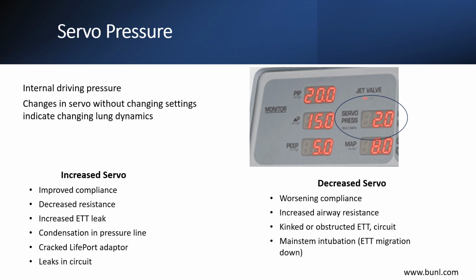This may mean that lung compliance is improving, or there is a leak in the system and gas is escaping. A decrease in the servo pressure indicates that less flow is required to fill a space at the same pressure. So, this means that for a given pressure, less volume is being delivered. This may indicate that lung compliance is decreasing, or there is an obstruction in the system.